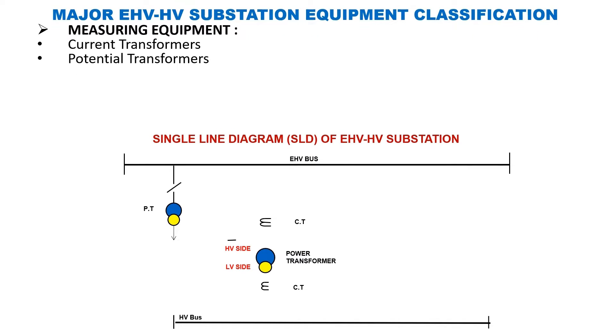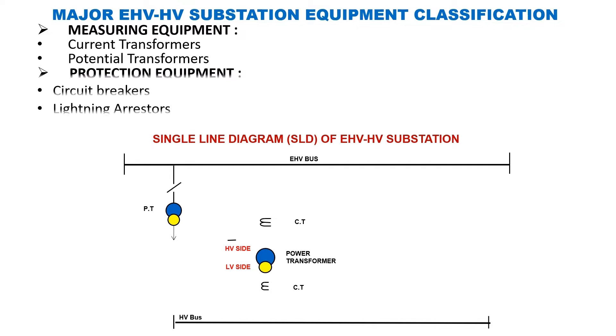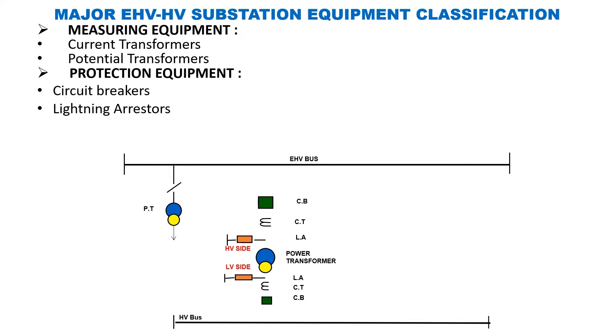Next are the protection equipment such as circuit breaker and lightning arrestors (LA). Lightning arrestors are always placed closest to the power transformer since its protection is of prime importance. Circuit breakers are placed as shown in the single line diagram.